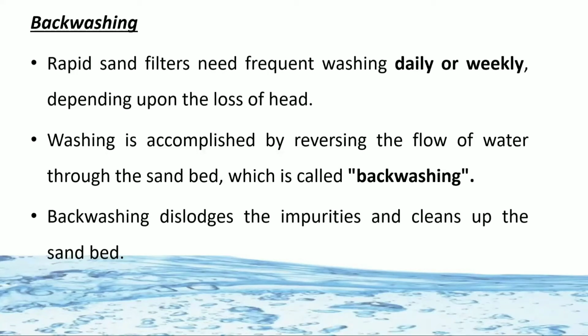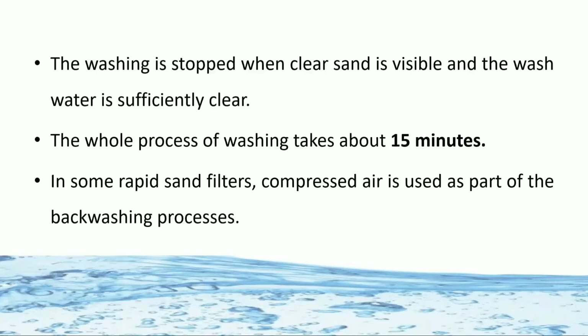Backwashing dislodges the impurities and cleans the sand bed. The washing is stopped when the clean sand is visible and the wash water is sufficiently clear. The whole process of washing takes about 15 minutes. In some rapid sand filters, compressed air is used for backwashing.